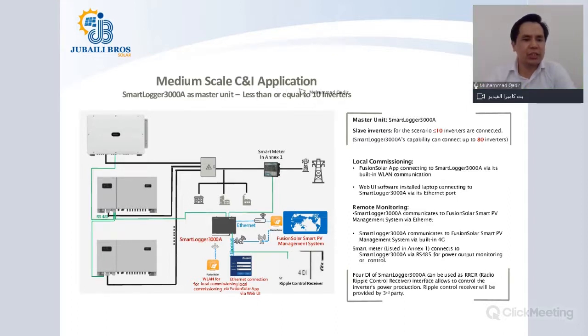Medium scale C&I application, again with the 100 KTL inverter, but here you will have a Smart Logger. For local commissioning, FusionSolar and WebUI, and for remote monitoring, FusionSolar and the SG5 FusionSolar web monitoring platform. In all these scenarios, the slave inverters are daisy chained either via RS485 cable or through Ethernet cable, because the inverter supports both types of cable connection, and the data is sent to the master inverter or the Smart Logger.